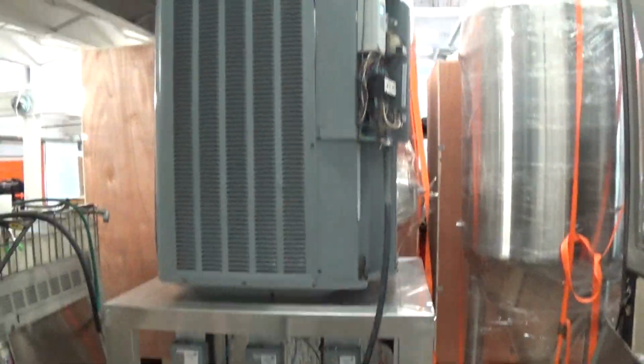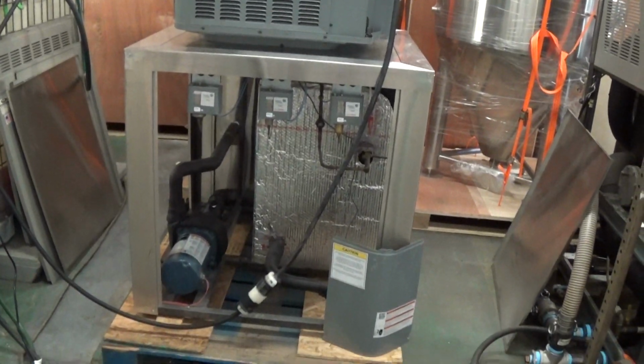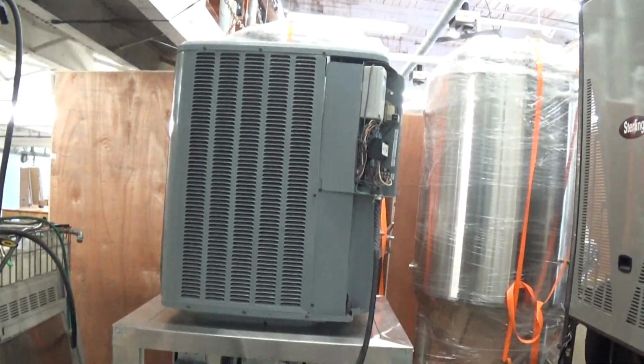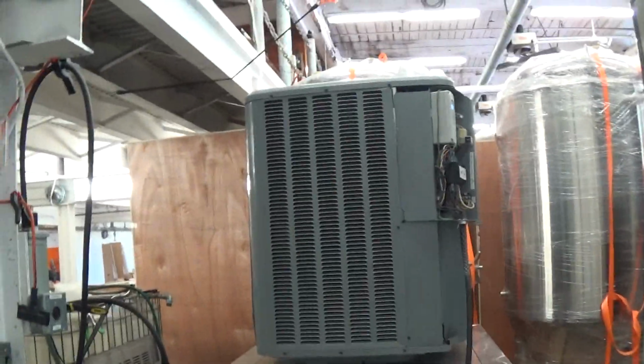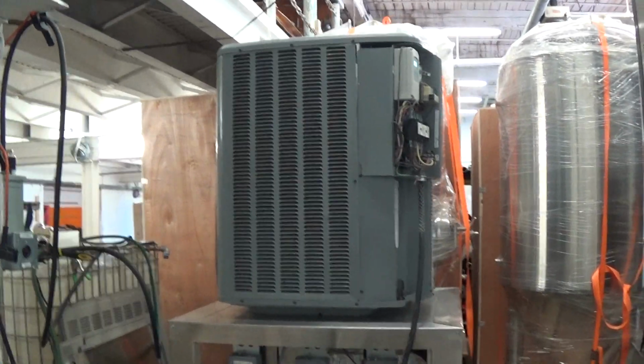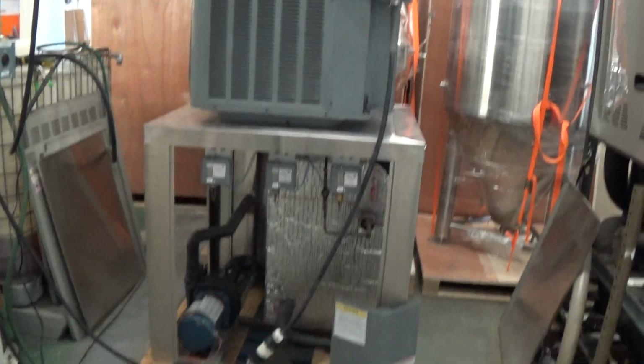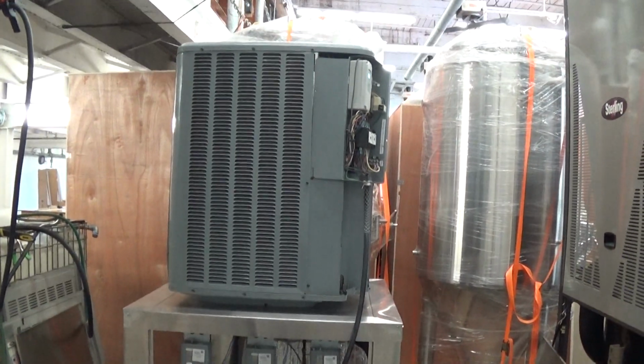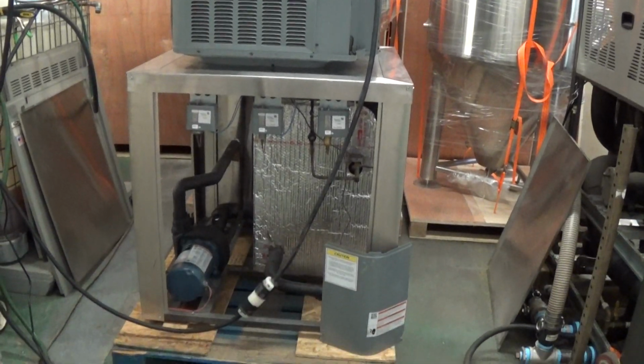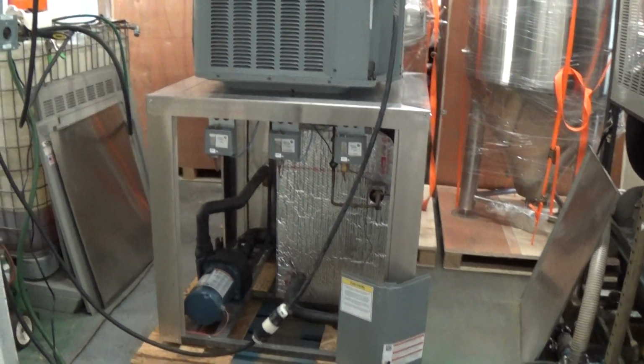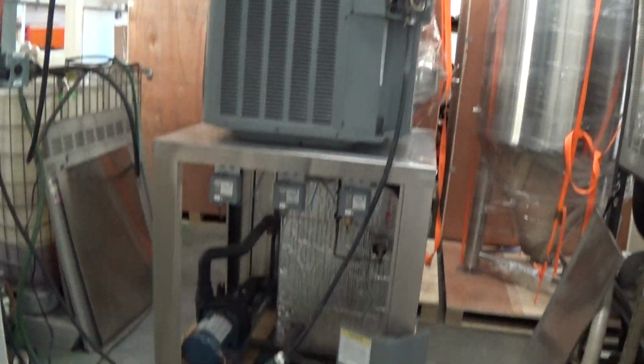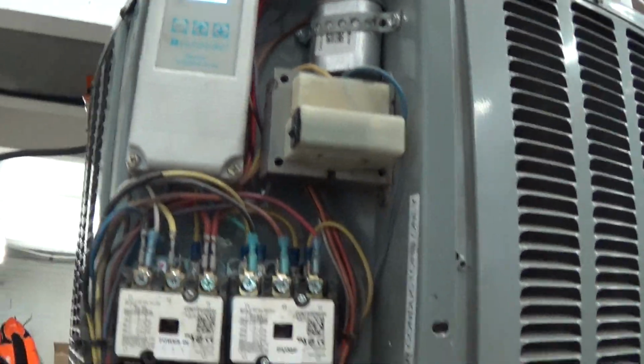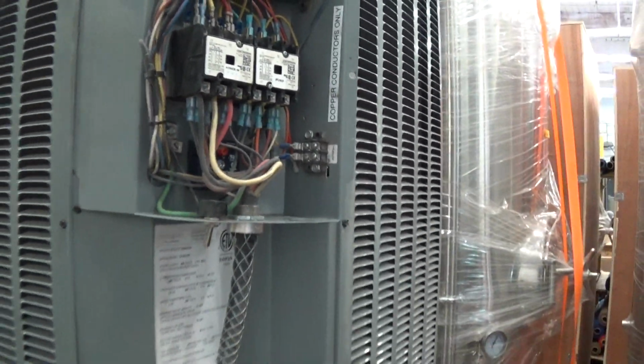Again, this is an outdoor rated unit, but you can put it indoors if you want. If you're going to run a fluid temperature below, say, 48 degrees, you do want to see glycol in there. The glycol percentage will depend on how low a fluid temperature you run, or on the outdoor climate if you put it outdoors. Even if you're running it fairly warm, it is always helpful to run a little bit of glycol, but there are a fair share of these out there running just straight water. So it's going to take a while for that volume to start cooling. We're going to come back to video number 2 as we approach that 50-degree set point.